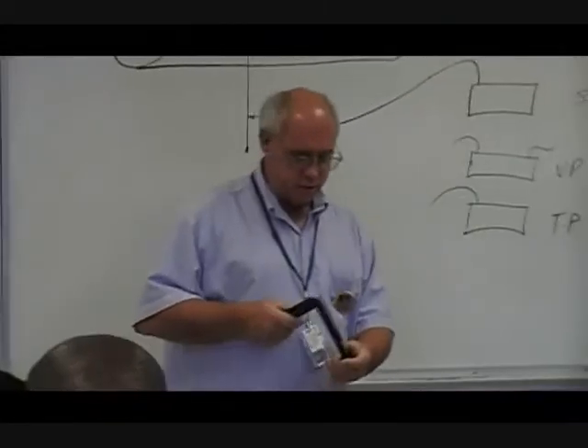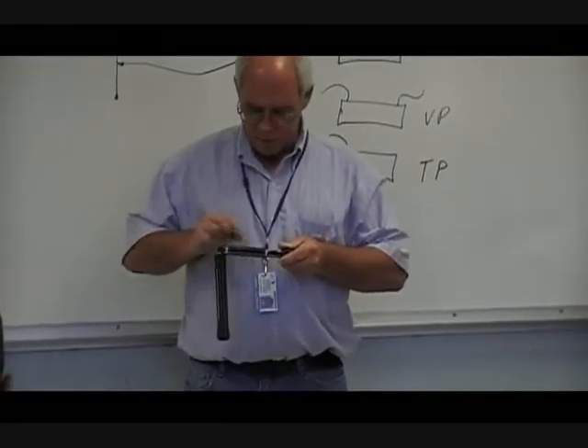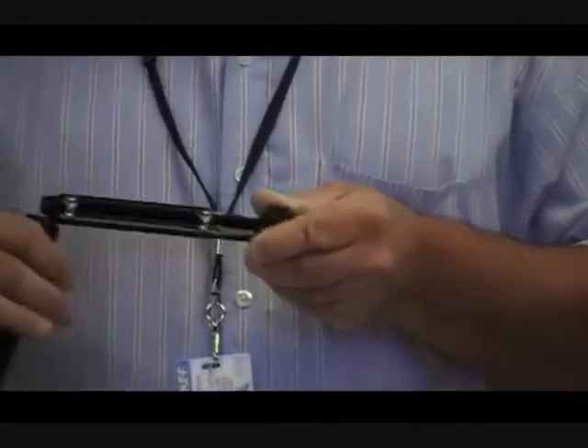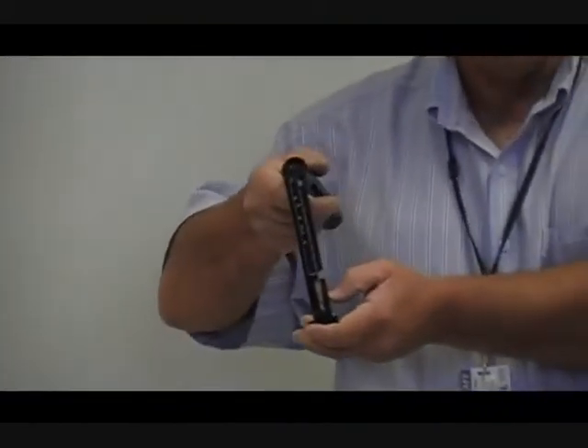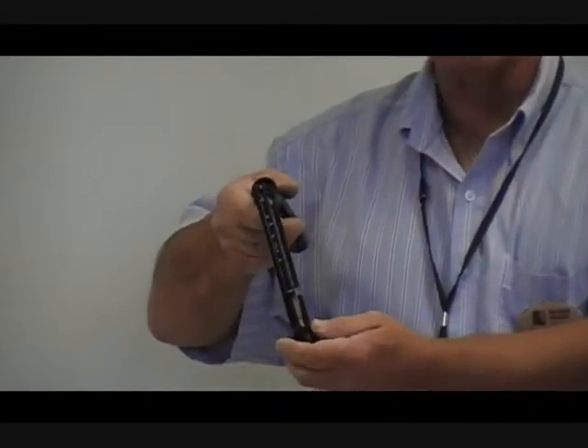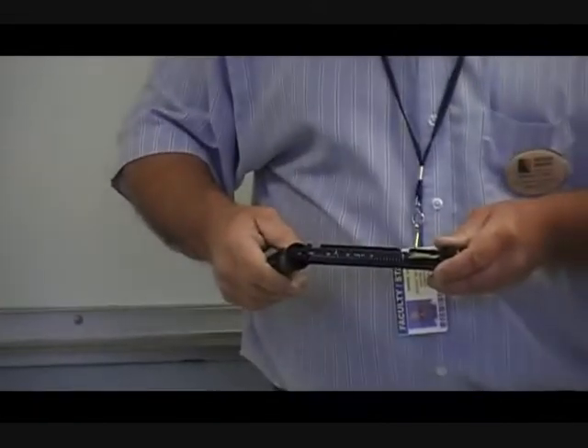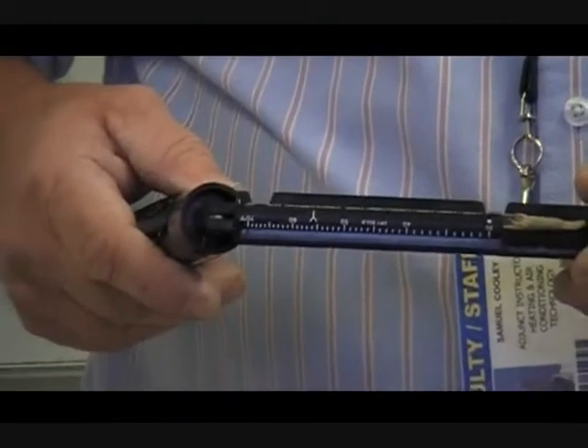Well, one way is through a sling psychrometer. The sling psychrometer has both a dry bulb, which is a regular thermometer, and a wet bulb, which is a regular thermometer with a wet sock on it. There's a little reservoir right here that holds water. By the way, the water needs to be at the room temperature, the temperature where you measure. You don't need to go get any hot water or cold water to put in there. You need to have water that's close to the temperature that you're going to be measuring the air in. And you're looking at the evaporation rate, which causes a dip in the temperature. If you go back and you learn about the evaporation, it takes energy to cause it to evaporate, where that energy shows up as a decrease in the temperature. This would be slung like so, that's the reason they call it a sling psychrometer, for about a minute. After about a minute, you would take and read the wet bulb first. In this particular case, I didn't sling it that long, but I've got about 63 degrees wet bulb and about 75 dry bulb.